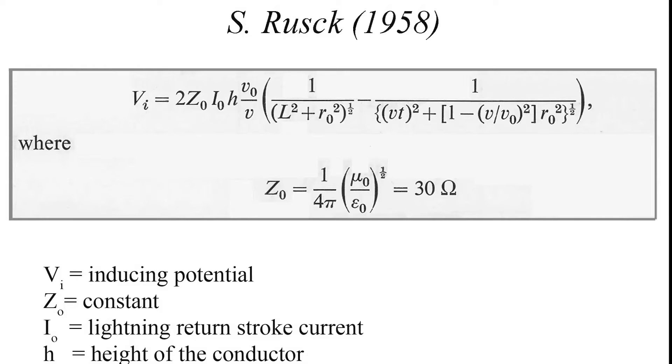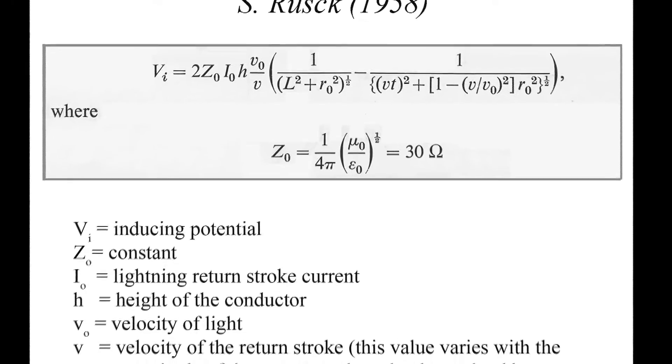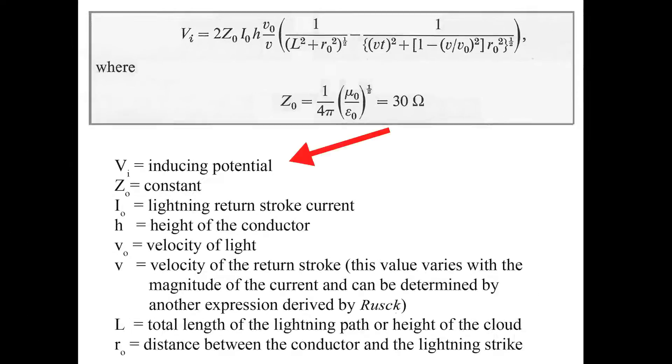The phenomenon is quite well understood, and 1958 saw the introduction of the Rusk equation, which is still widely used today and allows for the calculation of the inducing potential as a function of the return stroke current, the height of the conductor, and the distance between the conductor and the lightning strike.